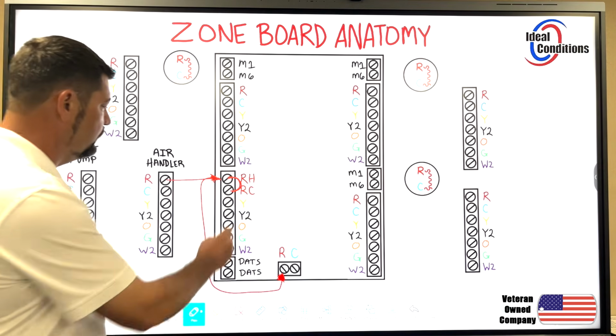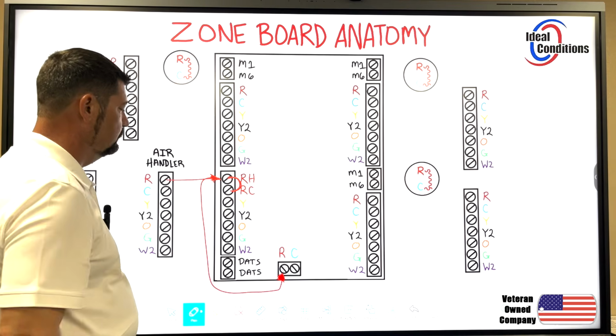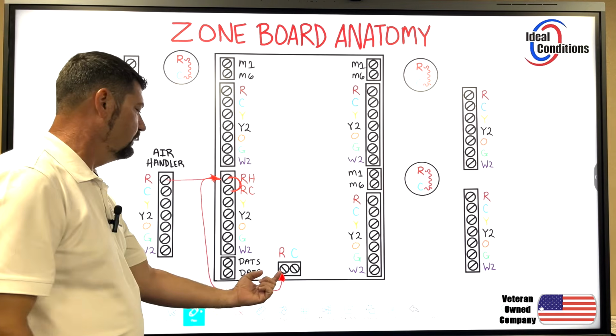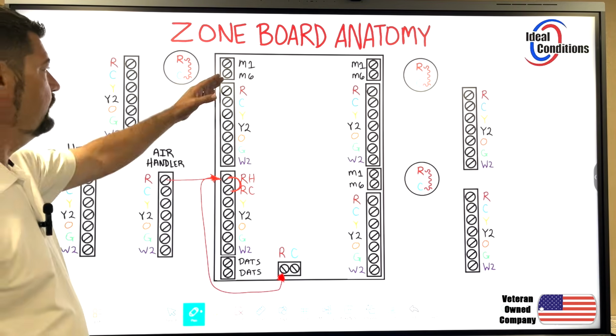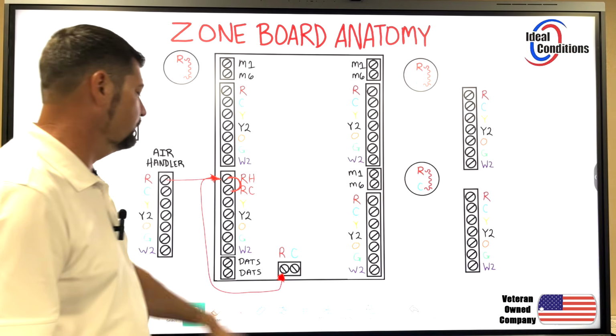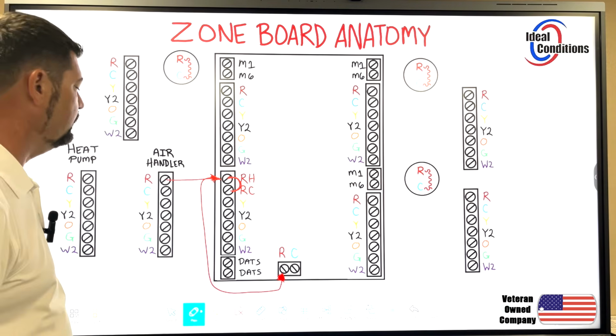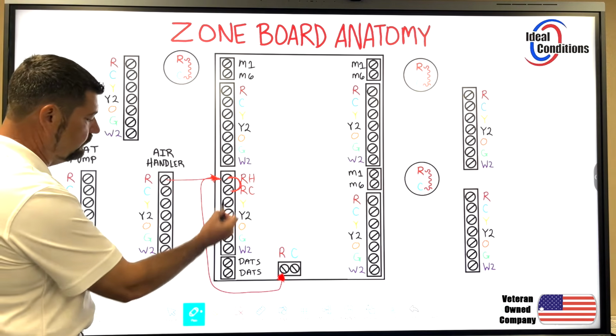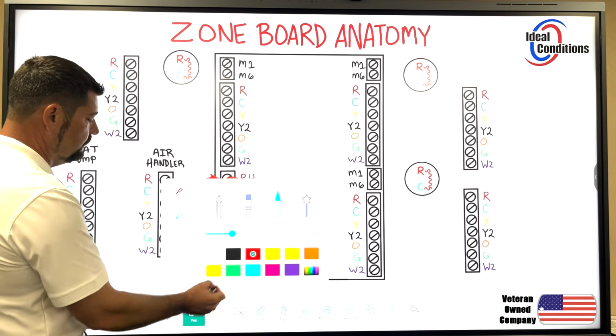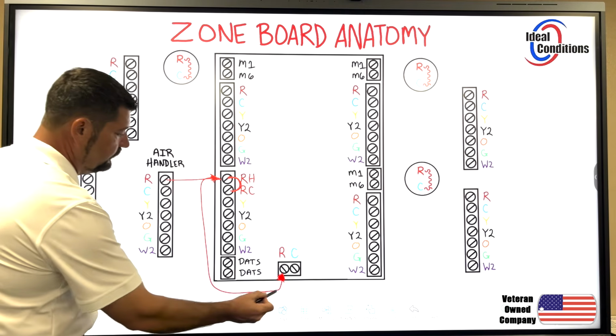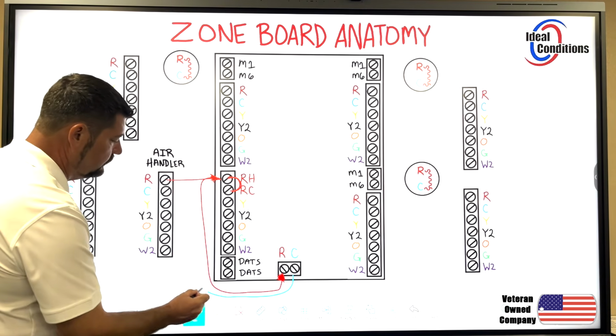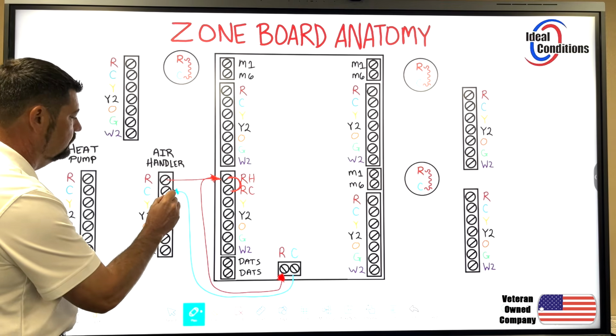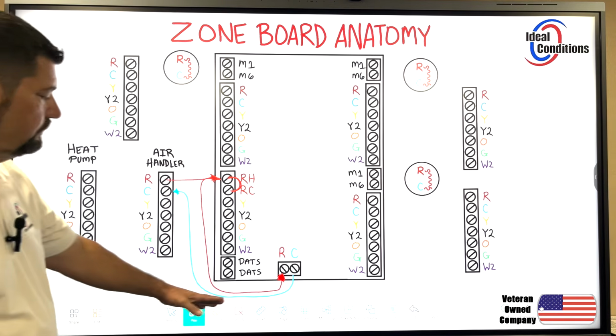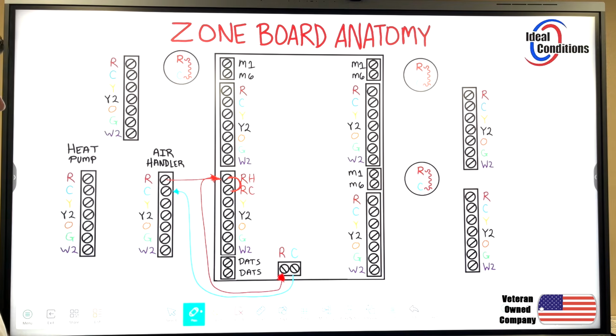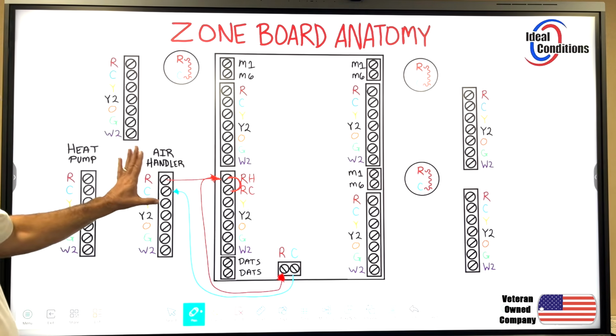I've got to come in so my equipment can relay the power back out, but I also have to power my zone board in parallel so I have 24 volts on all the corresponding terminals to send power out and receive power back. There's no common over here, but where you will need to put a common is a path back over here. Take note of that step—this is with a primary transformer, 75 volt amp, and there's no common to go here.